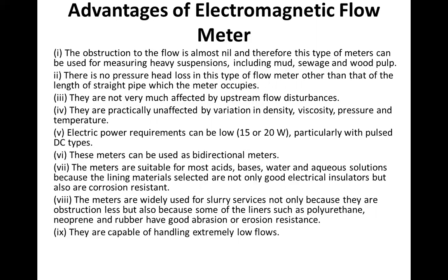The meters are suitable for most acids, bases, water, and aqueous solutions because the lining materials selected are not only good electrical insulators but also corrosion resistant. The meters are widely used for slurry services not only because they are obstructionless but also because some of the liners such as polyurethane, neoprene and rubber have good abrasion or erosion resistance. They are capable of handling extremely low flows.